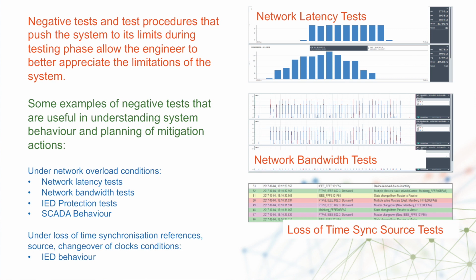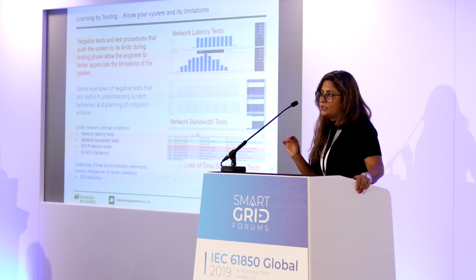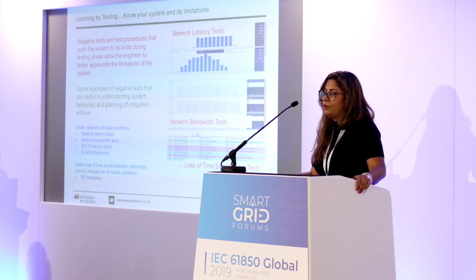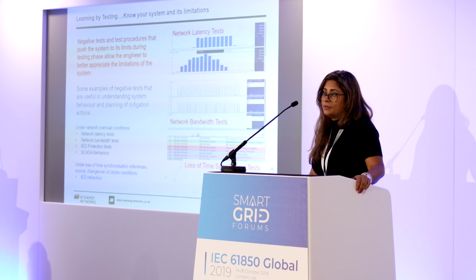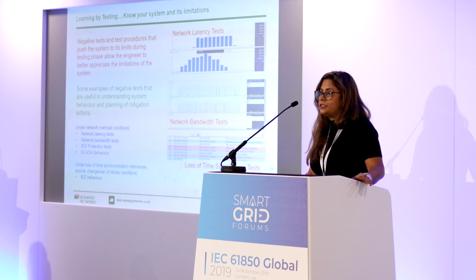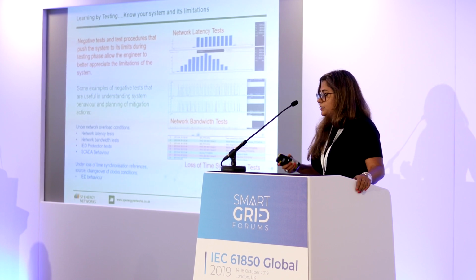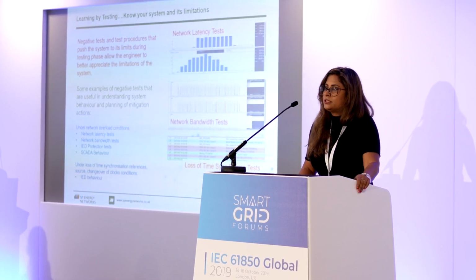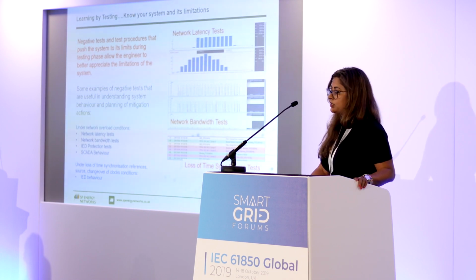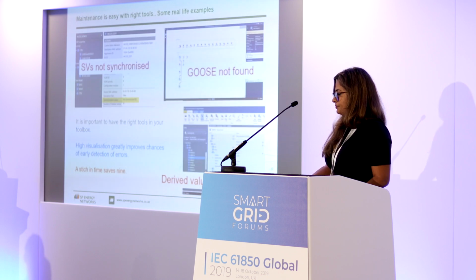That's the point where the system fails. We also saw different IED behaviors - some IEDs start complaining when their port receives more than 80 GOOSE messages per second, or something similar. These are limitations you won't face every day, but it's important to perform this test and document it, so that if a maintenance engineer sees erratic behavior on the network, they can refer to the system's known limitations and check if one has been reached. There will always be unexpected situations that arise when operating the system daily, so knowing the limitations of your system is key to both design, testing, and maintenance.